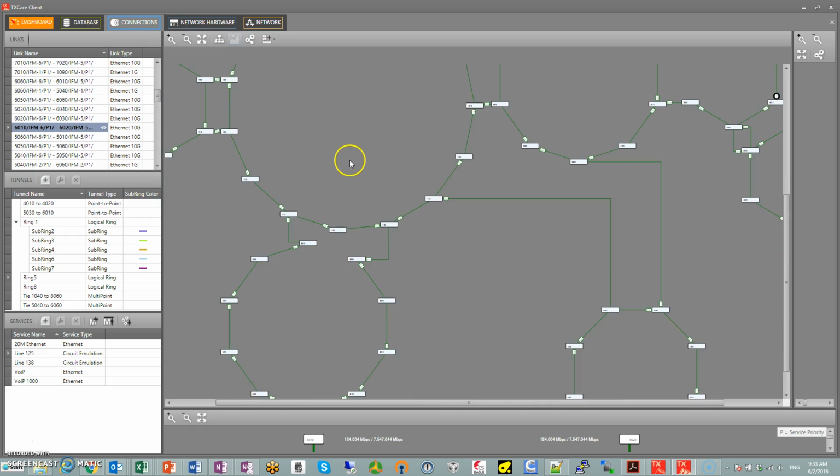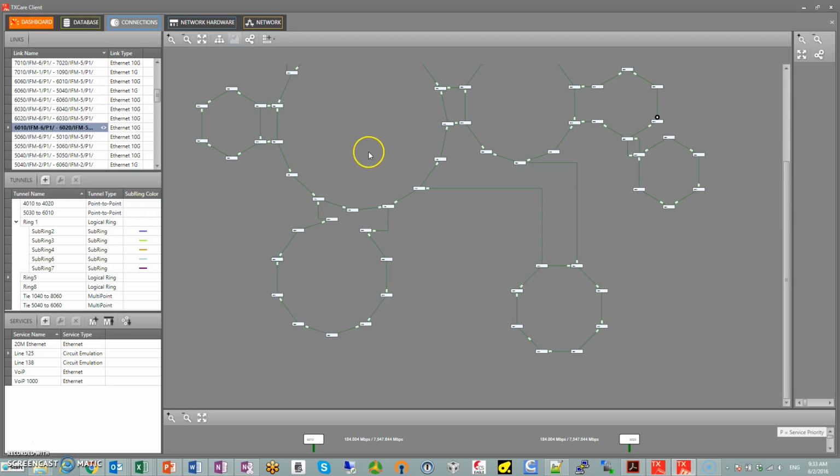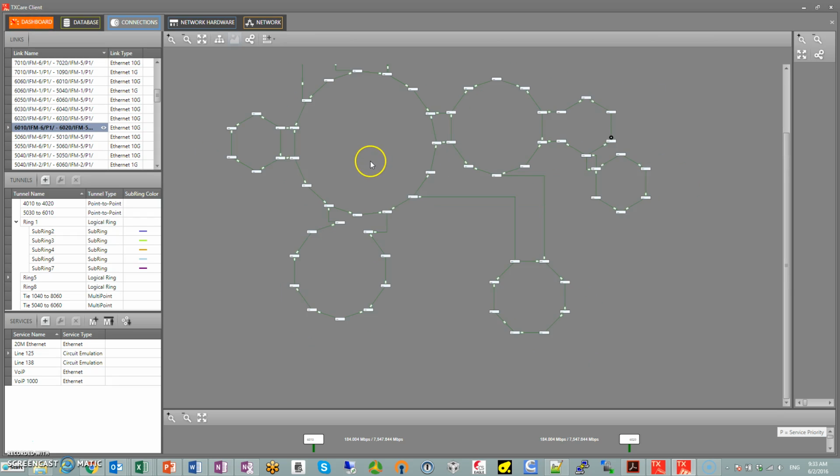SCADA tends to be a protocol that's sort of a poll-select type protocol. Even though Ethernet is becoming more and more popular, I think there's still a vast number of SCADA systems over point to multipoint RS232, with the advantage that point to multipoint 232 is basically non-routable.